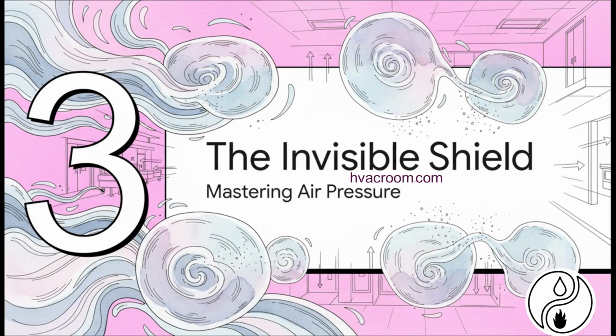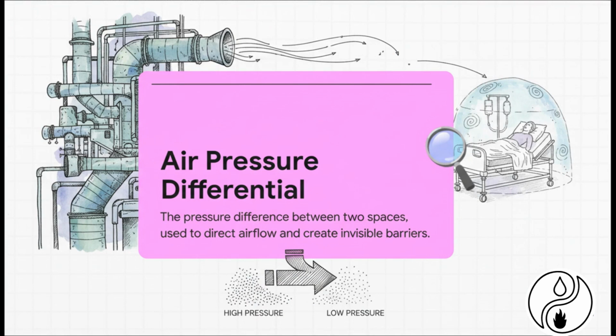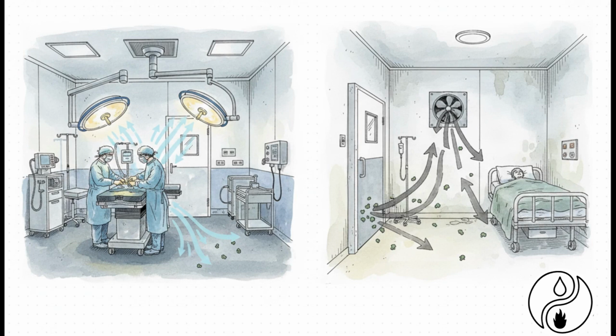But temperature and humidity are only half the story. The system also has to create invisible shields, using something you can't even see: air pressure. It comes down to something called an air pressure differential—the difference in air pressure between two areas. By controlling this with extreme precision, hospitals can literally tell the air where to go, creating invisible walls that protect everybody. This gets used in two critical ways.